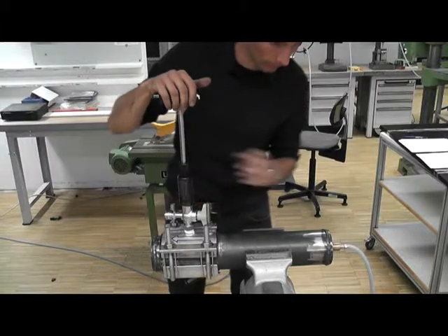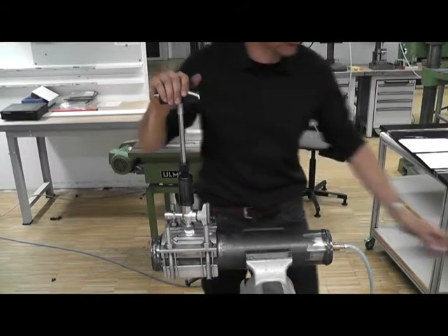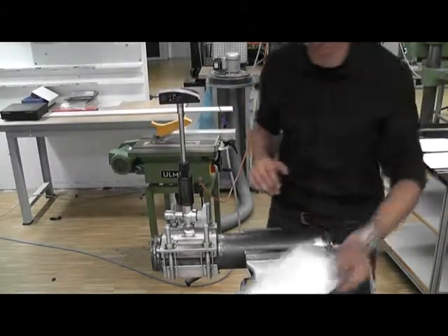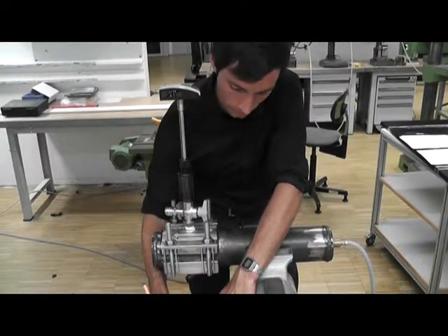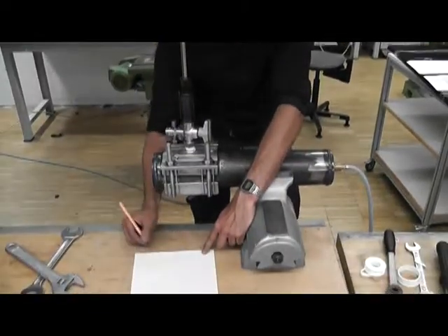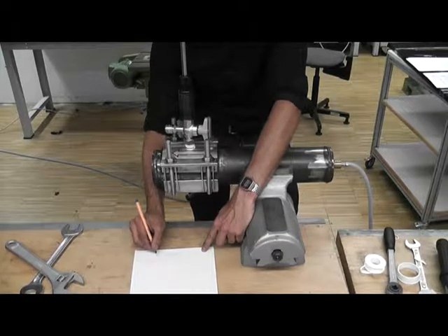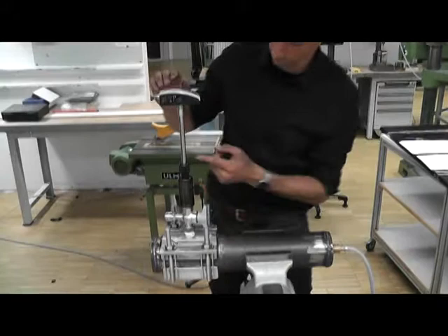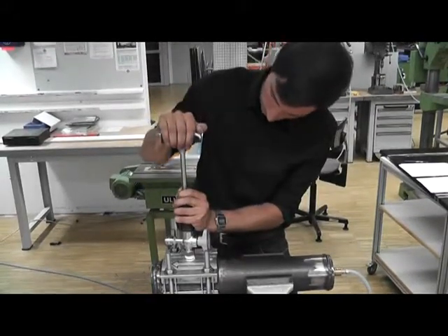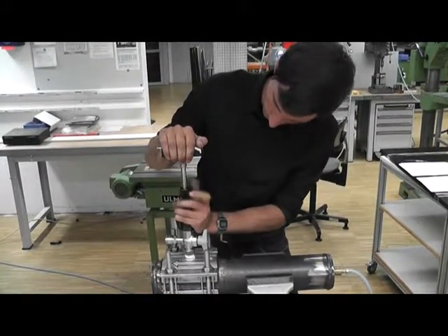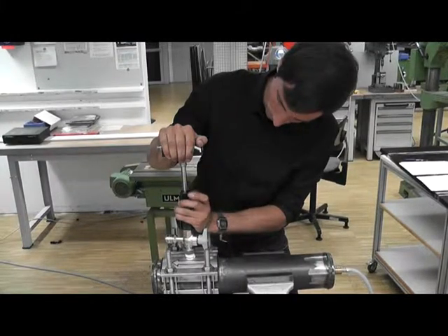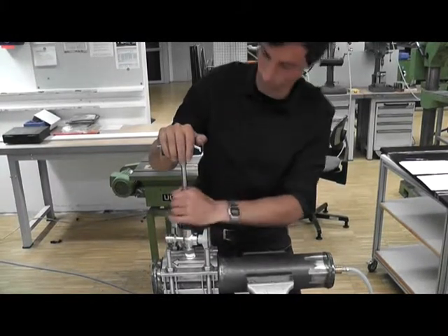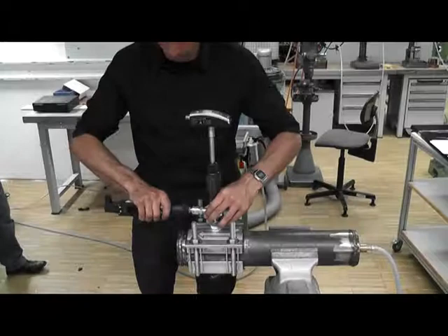Now we have to adjust the transmitter to the middle of the pipe. To do that, add the outer radius of the pipe to the scale you assigned before and adjust the transmitter to this value. Now the transmitter should be in the middle of the pipe. After the adjustment of the 6448, screw the scale of the transmitter tight. The transmitter is installed mechanically now, and after the easy electrical installation, the 6448 is ready to use.